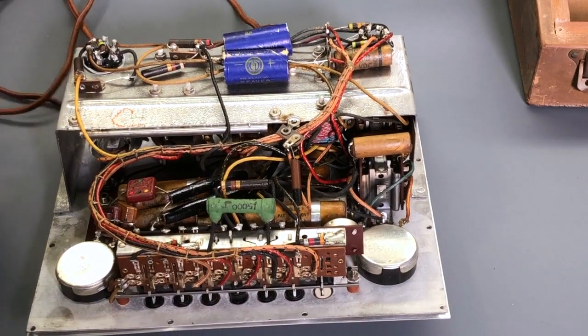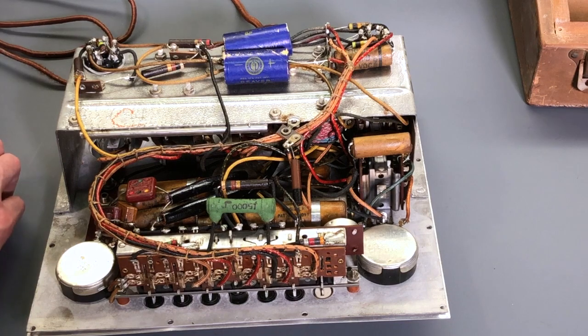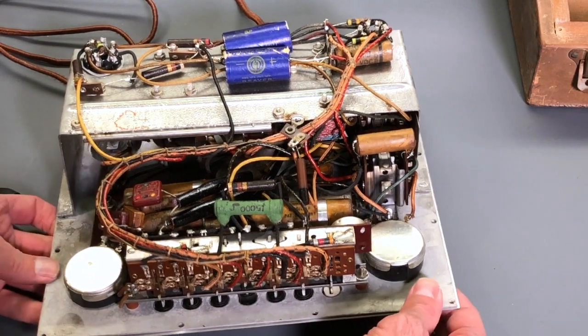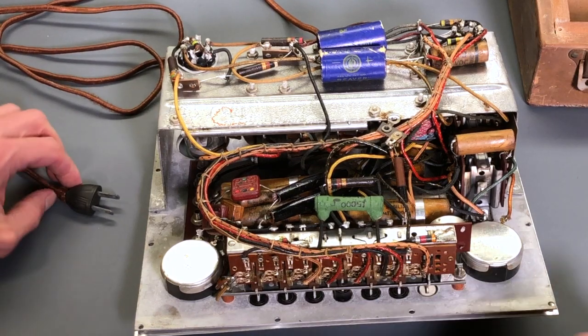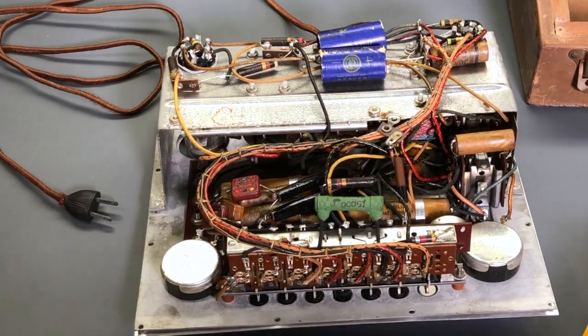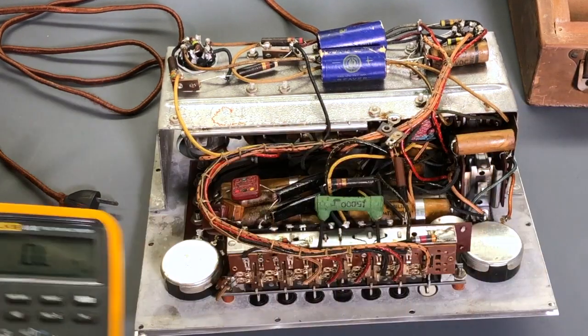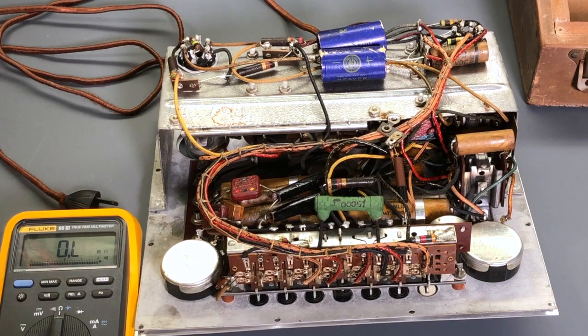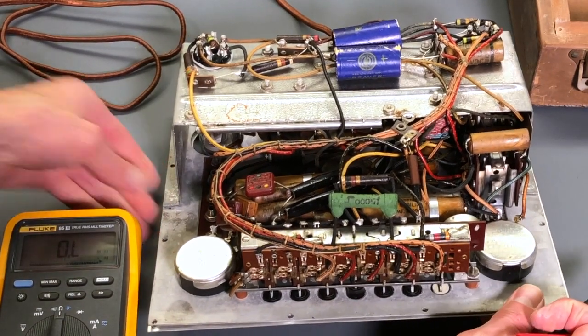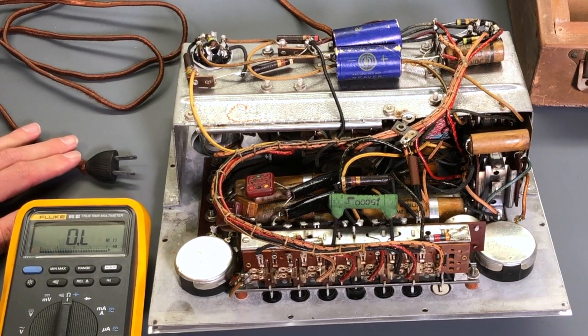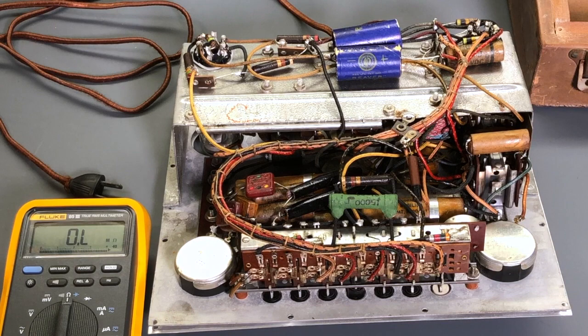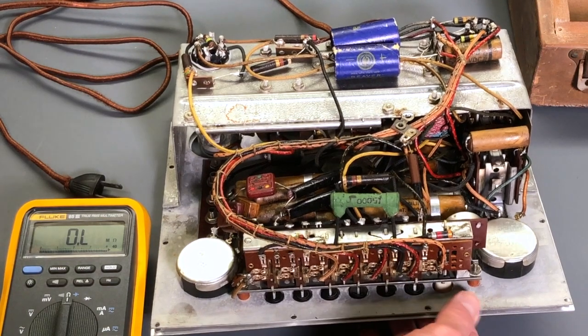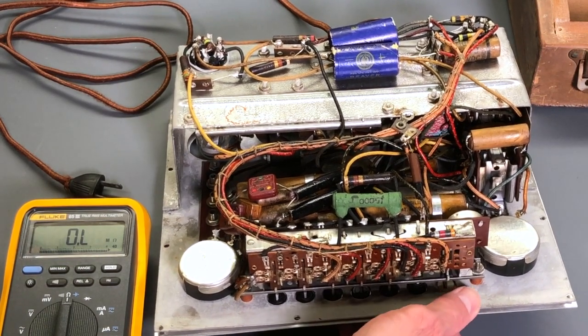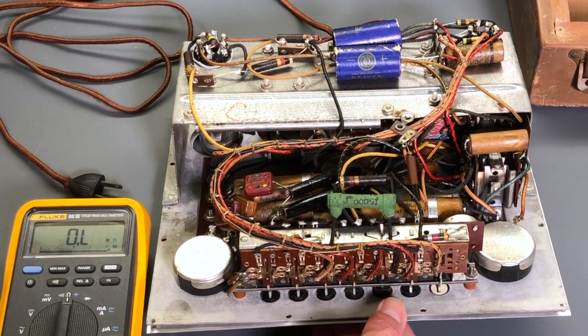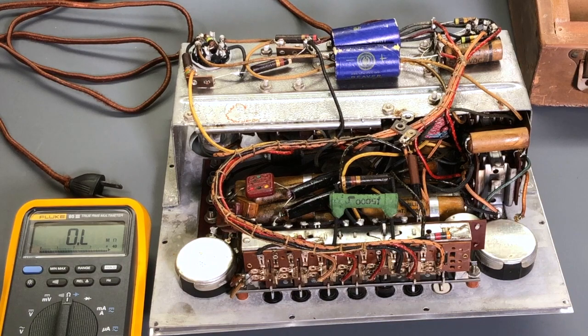So let's take a couple of measurements on here and see for the resistance. Let's start with the cord, and I'll move this over a little bit, and the meter here, see if we can get that into the shot at the same time. So we want to look for any serious short circuits. We're not going to want to put any power to the unit if there's a dead short, say on a transformer or something like that. So first of all, the power switch, I believe this white button over here was the on off, so go like that. I think that should put it in the on position.